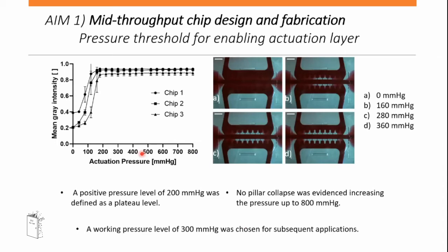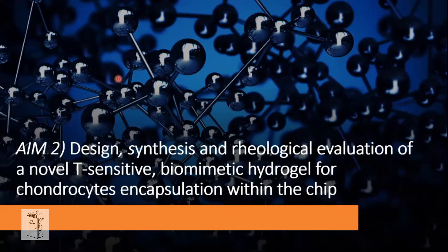The last step was to evaluate the mechanical stimulation at the micro-scale level — assessing how the actuation layer exerts the specific compression desired. A positive pressure of 200 mmHg was applied, and a plateau was reached. We decided to use 300 mmHg to exert total mechanical compression of the device.